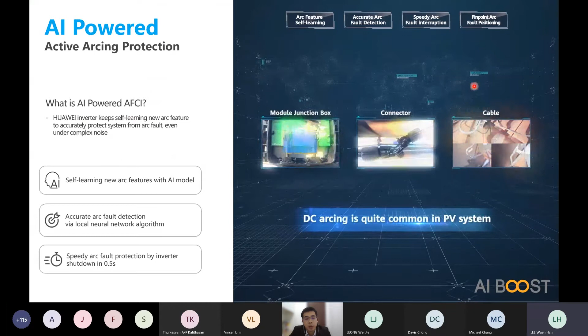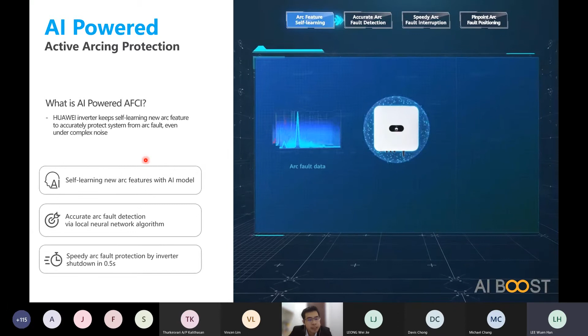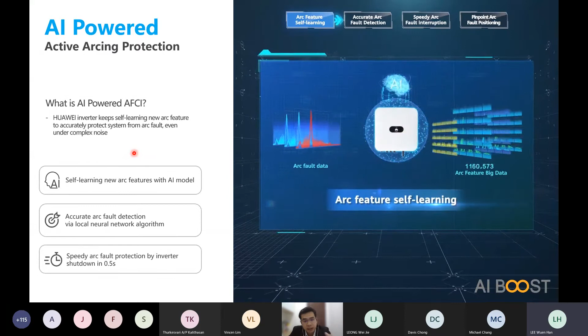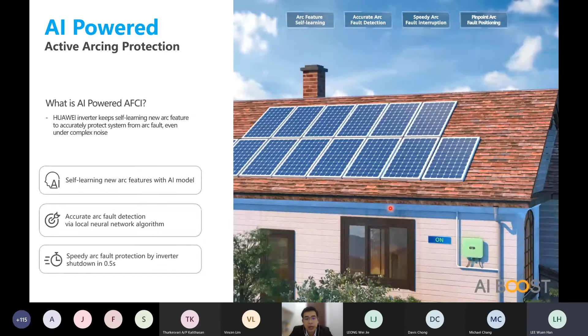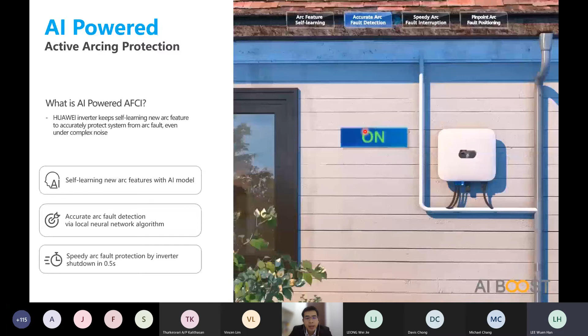So our inverter is equipped with this AI-powered AFCI. As I mentioned, these are the common problems that can cause arc fault. So our inverter has this self-learning capability to accurately protect the system from arc fault even under complex noise. So let's take a look at how it works. For example, we have an arc fault occurring in this particular panel. The arc fault happens here, and then the signal will be sent to the inverter.